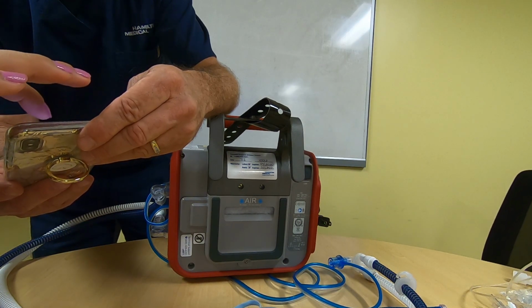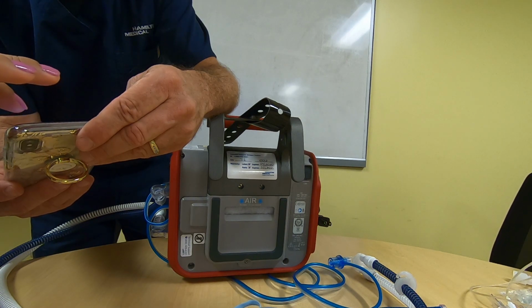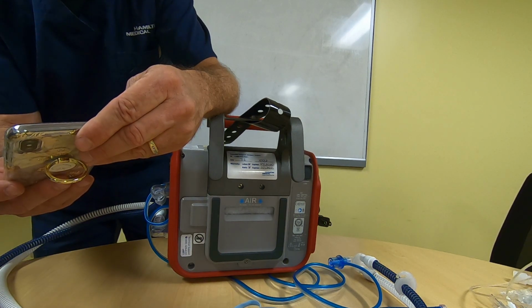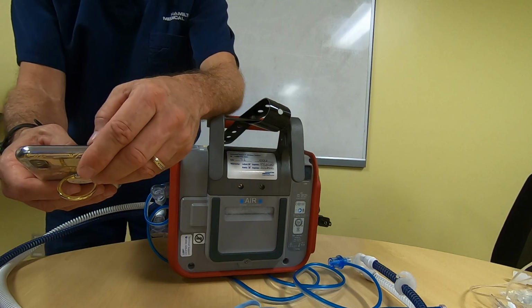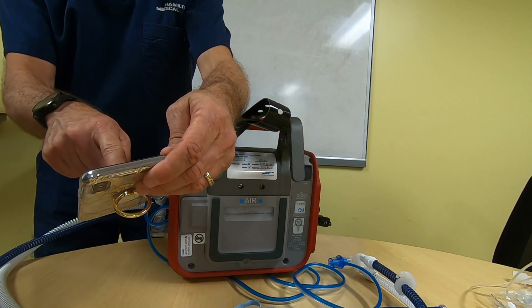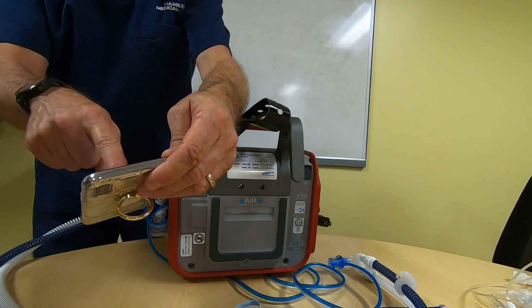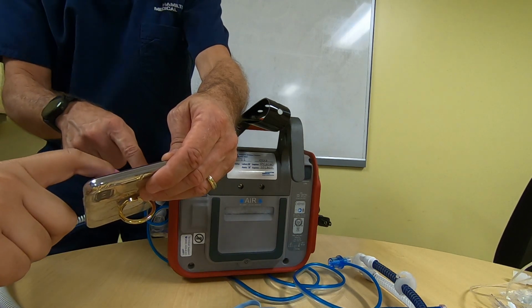Where's the sample, are you putting the sample line? Here's the problem with that. The Y is technically here, so your sample line's here, and you get mixed gases for your sample, not straight.